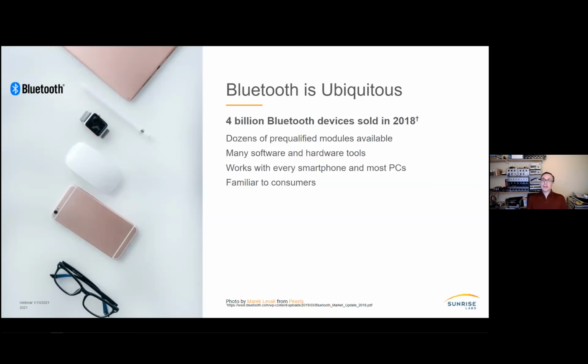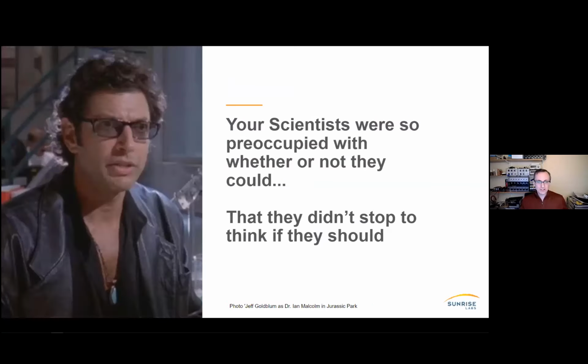On the FCC side, the FCC will certify modules, but it does not certify the system. The system still has to be certified separately. You may be able to sneak around certifying as an intentional emitter if the Bluetooth module is the only intentional emitter in your design, in your system. But that doesn't mean you get out of the requirements for system testing, which the FCC requires, which are largely the same as what 60601-1-2 requires. So if you're doing a medical device, you're doing that testing anyway, predominantly. So I'm already getting into gotchas. I haven't even gotten there yet.